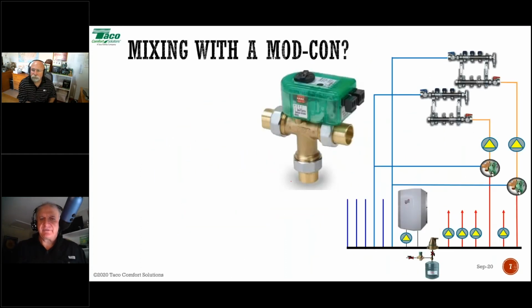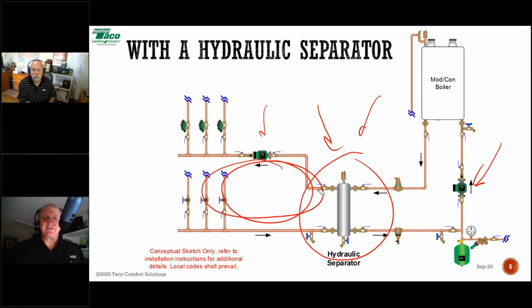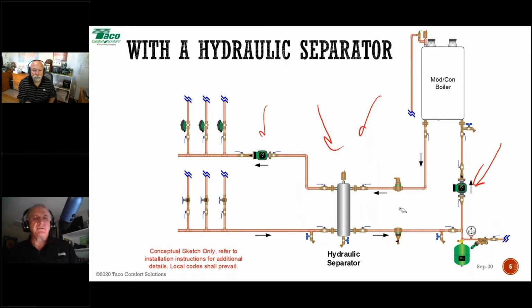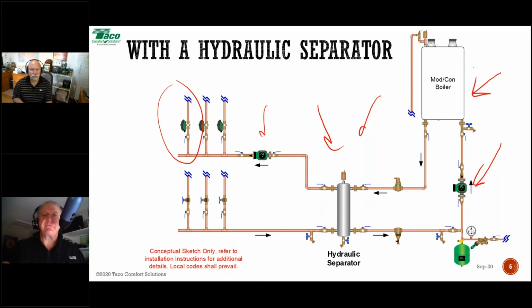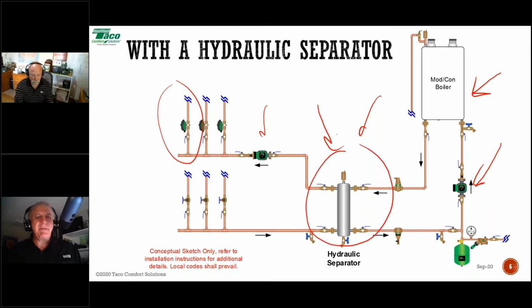If you have a system where you have more zones and maybe the load of the smallest zone is within a few thousand BTUs of the lowest firing rate of your boiler, that hydraulic separator with a little bit of mass to it, with some water content to it, is going to be of a benefit to you to help reduce the likelihood of short cycling.